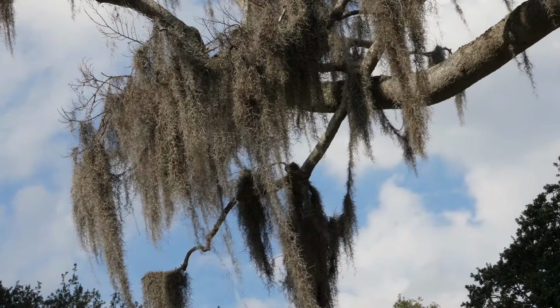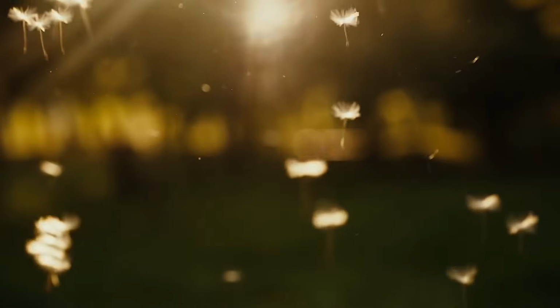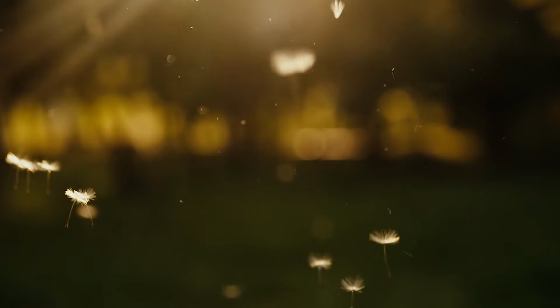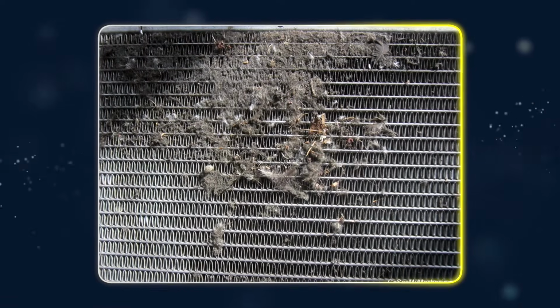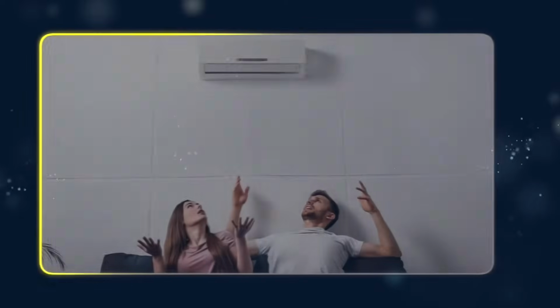We see this especially in areas where people have trees that put off a lot of pollen, and when they drop that pollen, or trees like weeping willow or cottonwood, they tend to clog up the condensers very quickly and cause a lot of issues. And so normally when we start getting AC icing service calls in the beginning of the summer, we know that it's because of a combination of the pollen clogging these condensers and or it was just a really dirty condenser that hasn't been cleaned in a while.